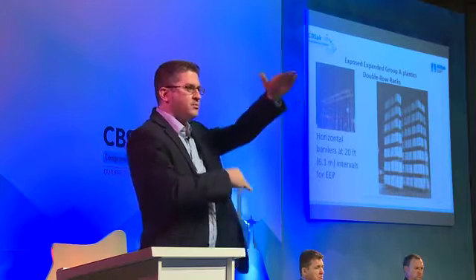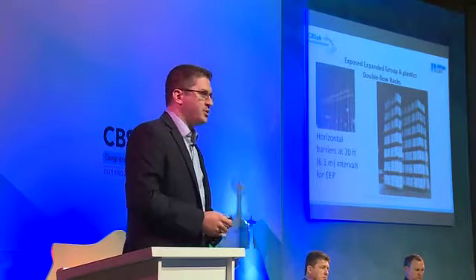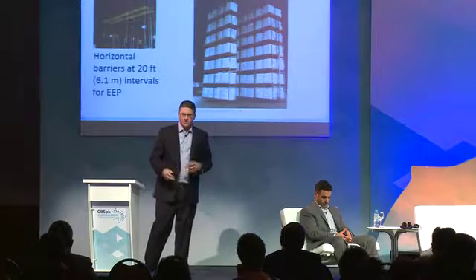in a 12-meter tall space, and see if that 1 level of in-rack sprinklers, along with the ceiling system, can deal with an exposed, expanded plastic commodity. And that commodity, Carrie's going to show you an awful lot of tests with that, but if we're looking at the screen here, it's a little hard to tell what that is, the white commodity on that rack.